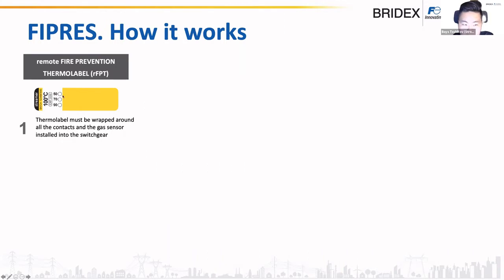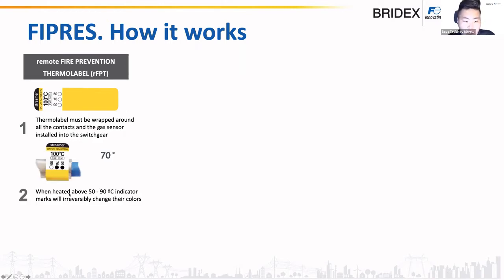It's a sticker. It has two parts, a yellow part and a white one. The white one has these 3 thermal indication dots, and the yellow one has signal gas encapsulated inside. So there are millions or billions of microcapsules with safe signal gas inside. This sticker should be glued to a contact connection or to the bus bar or to a cable lug, and the gas sensor should be installed in the same volume. When the contact heats up to, let's say, 70 degrees, the dots irreversibly change color to black. It's a one-time indication, and even if the temperature drops down to 20 degrees, the dots will remain black. And it gives clear information to maintenance personnel that something happened since the last visit.